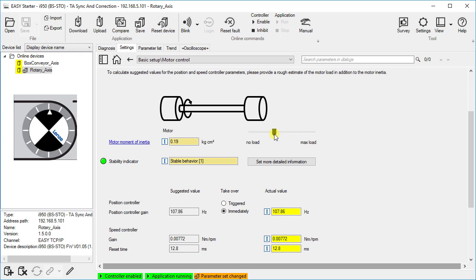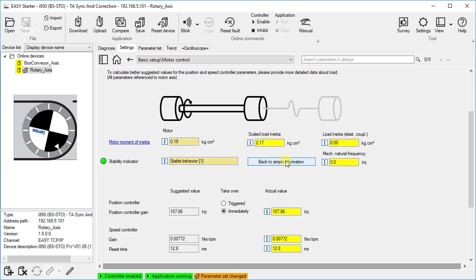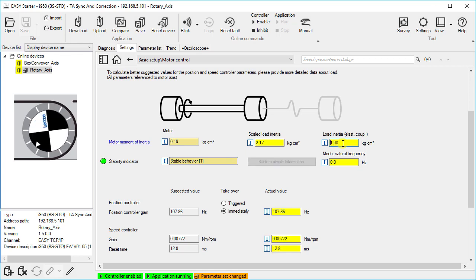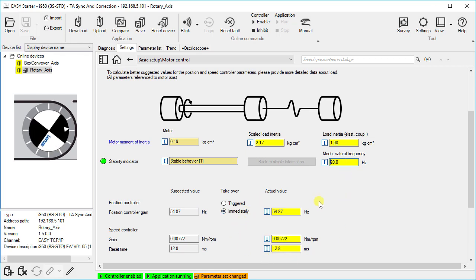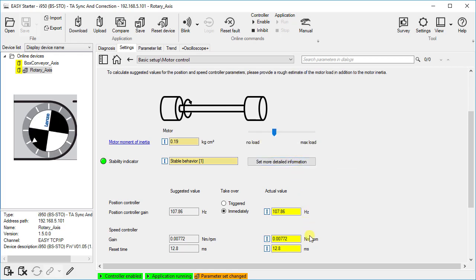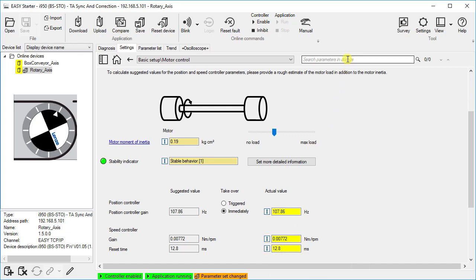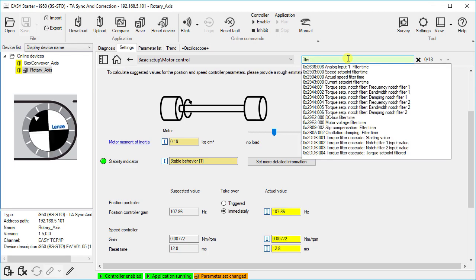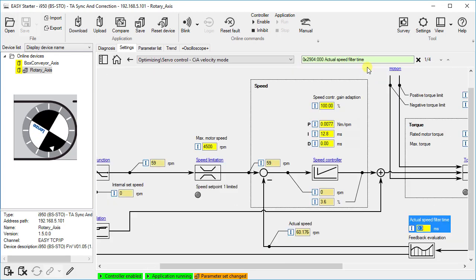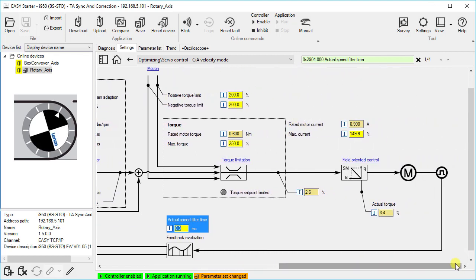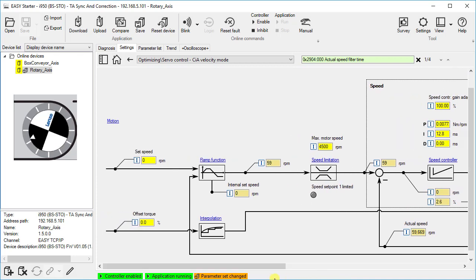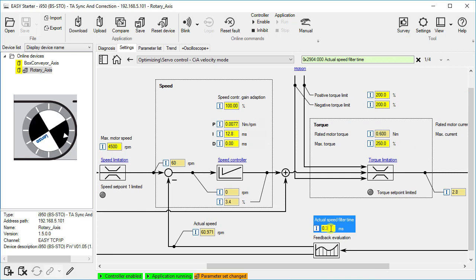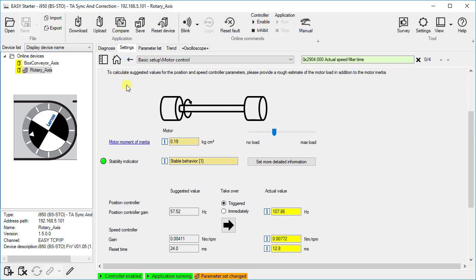If you know the load mass inertia of the machine, you can use the set more detailed information button to directly enter the physical values for calculation. For detailed input, not only the rigid coupling but also the elastic coupling of the load is considered. In this case, it is necessary to specify the mechanical natural frequency. The optimal reset time of the speed controller is primarily dependent on the filter time of the actual speed feedback. Any change in the actual speed filter time is automatically considered when calculating the speed controller reset time.